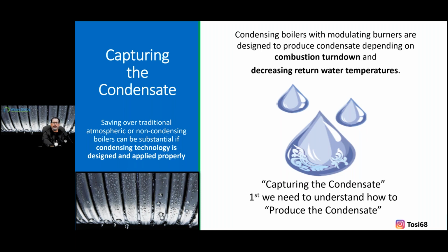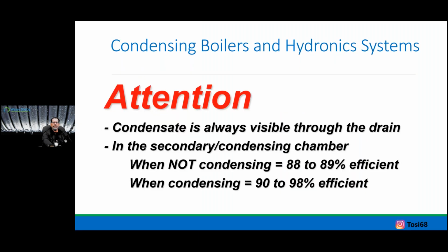We can do something far less, taking advantage of that cooler water now coming back to our boilers, condensing, collapsing, and now capturing and collapsing the condensation, right? And this is just a make or break line here. If we don't want to do outdoor sensors, if we're not even going to be in a condensing state, because I'm just going to peg to 190 degrees and let this thing run like we've done for the last 100 years or more, you're achieving some efficiencies, but you're not taking advantage of what you paid for or what was paid for or what was even sold.